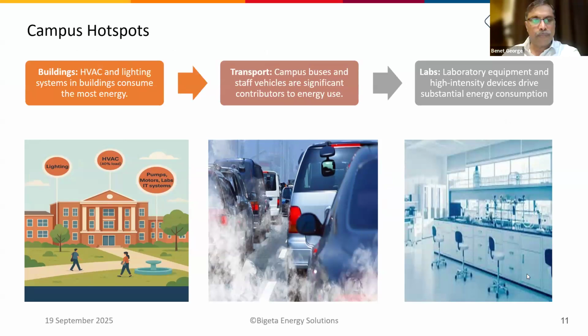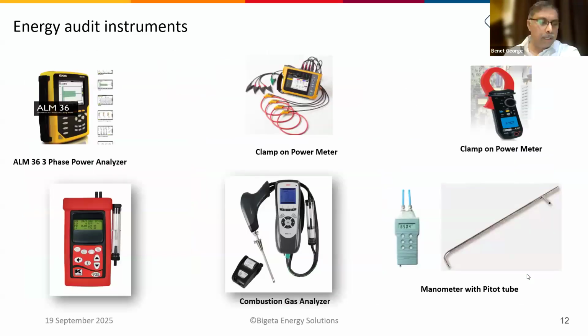And typically, the hotspot areas are buildings, transport, and labs, which may be the largest GHG emitting areas. An energy audit always involves various types of instrumentation. When you talk about electrical measurement, it can be power quality analysis, which can measure and record various parameters: voltage, current, power factor, energy, reactive power, etc. This is useful for measuring variable load applications. For example, the main incomer, or what is the variation of the demand, and demand has an impact on your energy bill. Or what is the variation of the power factor, the day and the evening or night base load conditions. Or the air conditioning system, how is the variation? Or UPS, what is the loading?